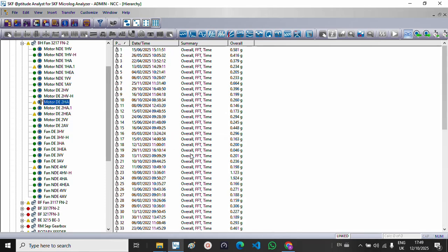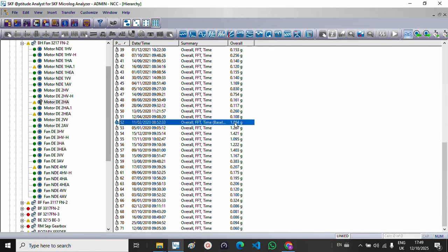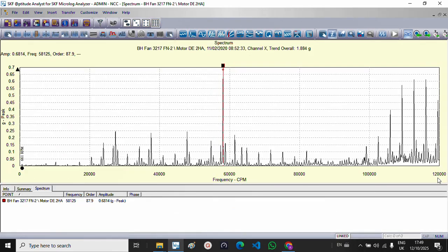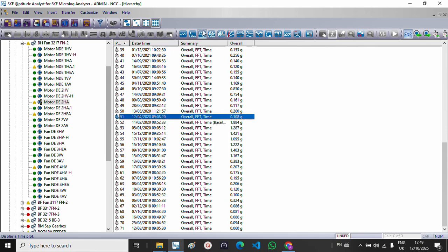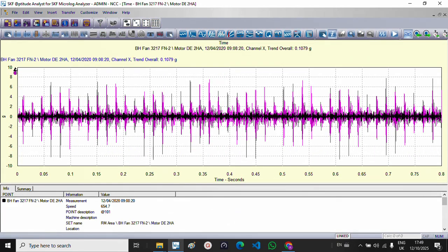Also, if we check the acceleration, what about it? CBM 1.8 g with the acceleration filtered at 2 kilohertz, which equals 120 thousand, where we can see here all this is the impact, and we will see this in the new one, how we can compare it.